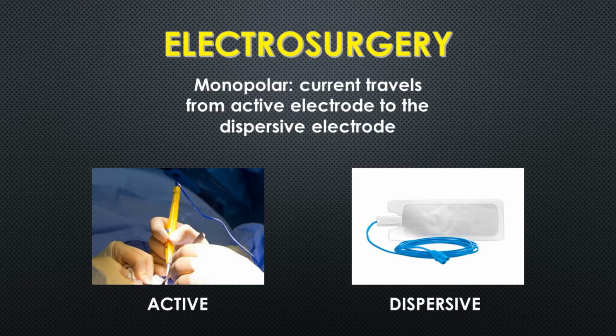In electrosurgery, there are two energy delivery modalities, monopolar and bipolar. In monopolar electrosurgery, the current travels from the active electrode to the dispersive electrode placed on the patient. In this case, the active electrode is the Bovie pencil the provider uses to cut or coagulate tissue at the surgical site, and the dispersive electrode is the grounding pad that we place on the patient.